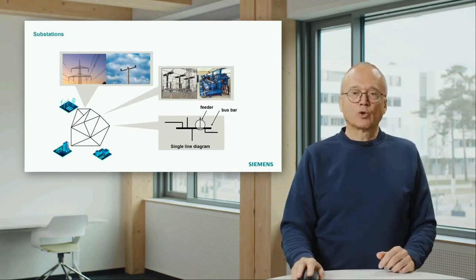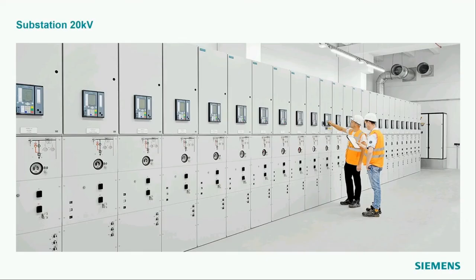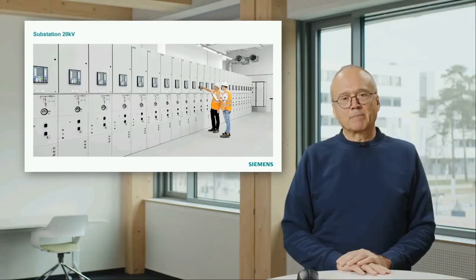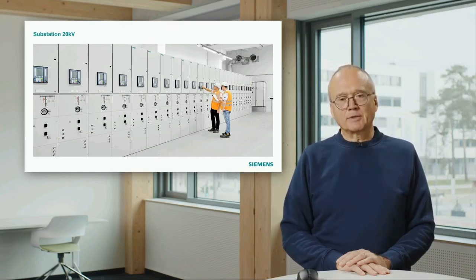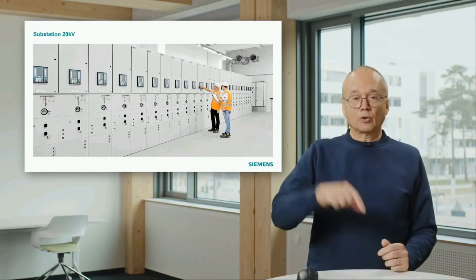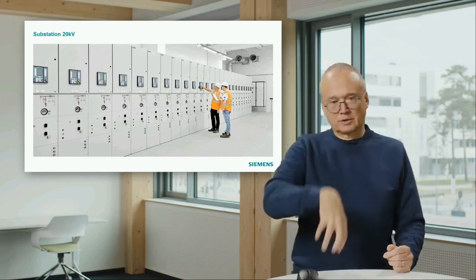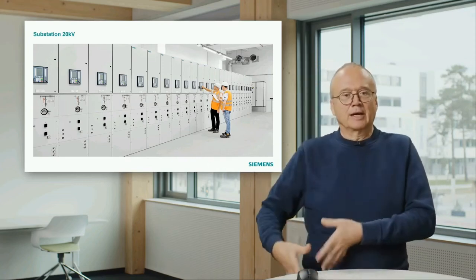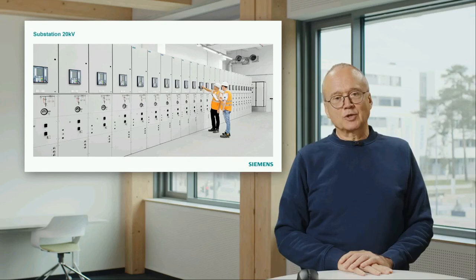The next slide shows the same story for a distribution level for medium voltage. In this case, it's an indoor substation. You see here the bus bar goes through this whole installation from left to right. It's a big substation, and we have many compartments there. In every compartment, you have one circuit breaker. The outgoing feeder goes down to the bottom. That means the cables are underneath. And you also see the protection relay installed there.